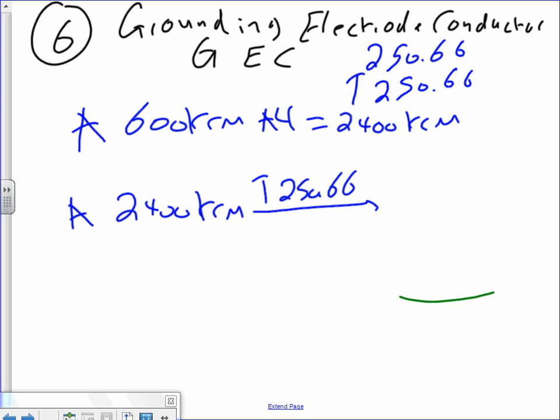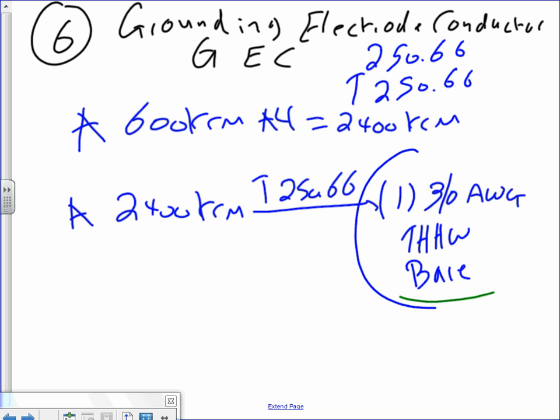Okay, so do I need to use 12.5% here for the grounding electrode conductor? No, you don't need to. So if you guys go to 250.66, please go there and highlight that table. You're going to end up, my friends, with one conductor, the largest, which is 3-aught AWG, THHW, or bare. Can I emphasize, guys, when you deal with grounding and bonding, the conductor can be bare. No insulation there. Or insulated.